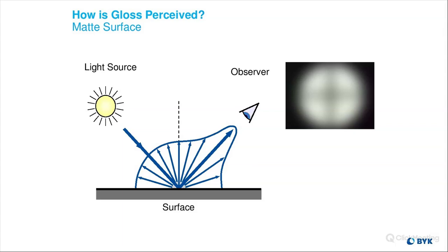When measuring with a 45-0 instrument, gloss is part of the measurement, so it measures color as we see it and it will affect your values. With a sphere instrument, it takes the gloss and the texture out of the equation and reads pure pigment. So it depends on the type of geometry of the color instrument that you're using.